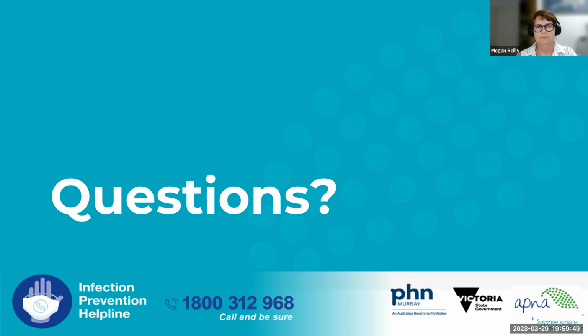Exactly. Yeah, fantastic. Belinda's asked, is there a minimum time between instruments being dirty to when they're being cleaned? That depends a little bit. There's no prescriptive time. Again, it will depend on the instruments that you're using, how complex they are, the procedures, how soiled they become. If you're doing that pre-treatment, which is certainly best practice at patient side, so damp wiping or dry wiping, that's going to significantly reduce the soiling and the bioburden. So you'll have a little bit more time before you can actually then move into the manual or the automated cleaning.